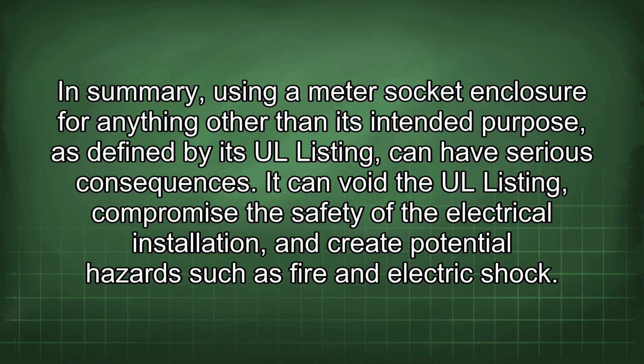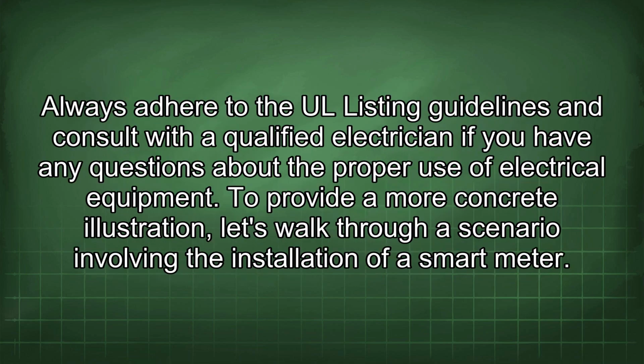In summary, using a meter socket enclosure for anything other than its intended purpose, as defined by its UL listing, can have serious consequences. It can void the UL listing, compromise the safety of the electrical installation, and create potential hazards such as fire and electric shock. Always adhere to the UL listing guidelines and consult with a qualified electrician if you have any questions about the proper use of electrical equipment.